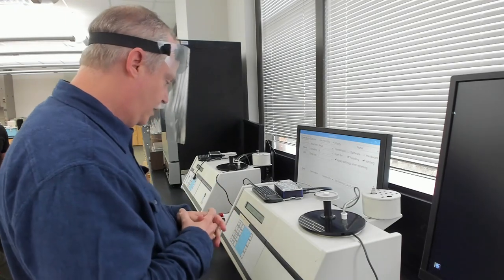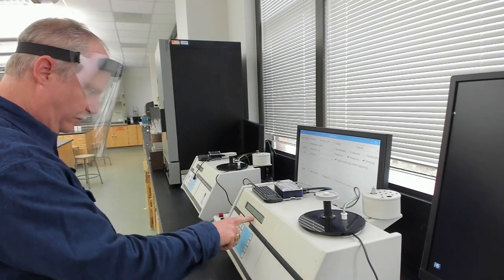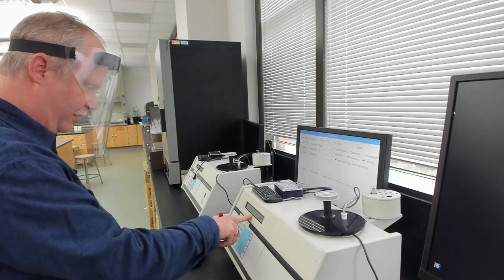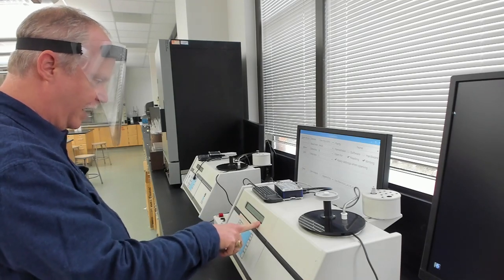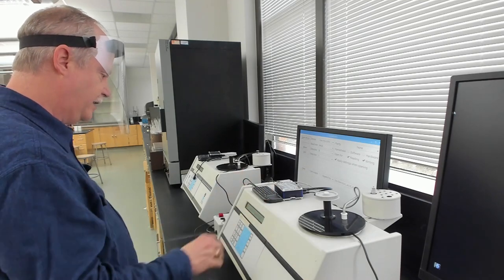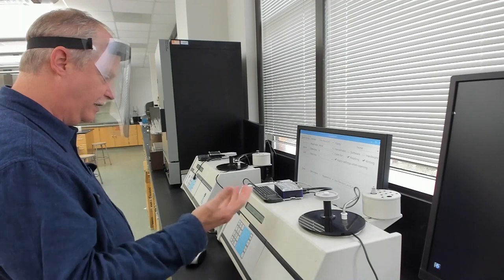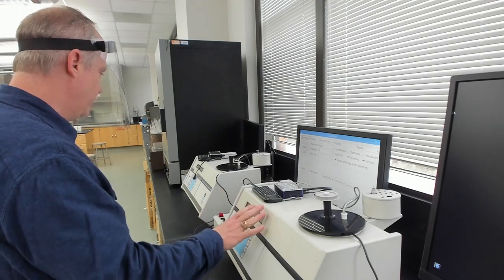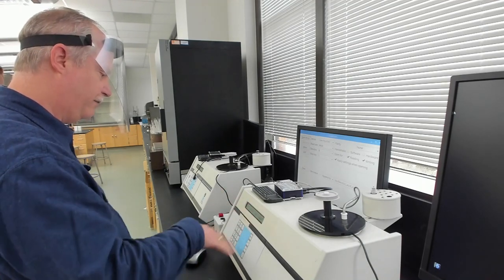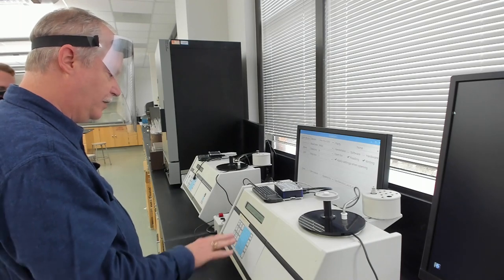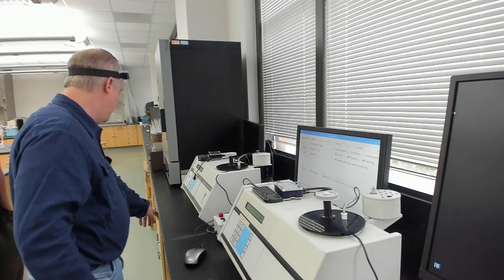So now this one says here, error 2300, cold restart, RAM disk erased. And that's what I was saying about that. It doesn't have a good battery in it. And so every year we have to start these up, and then we have to sort of reconfigure them using these star codes on the front. And the manual is right here.